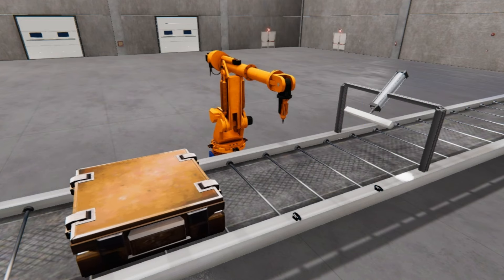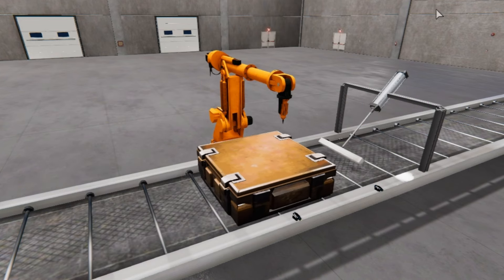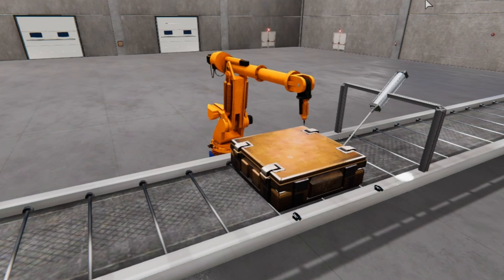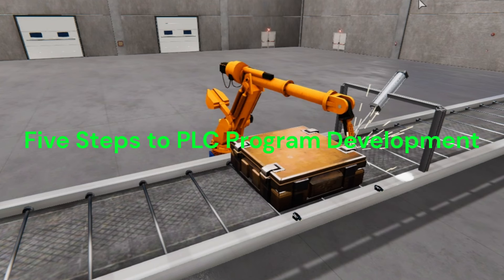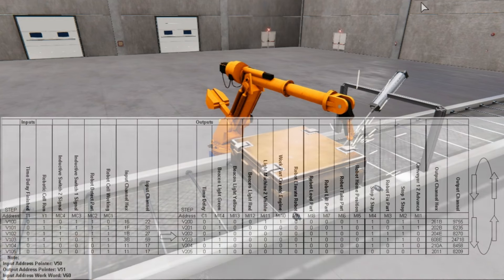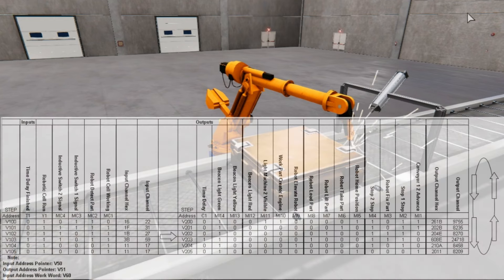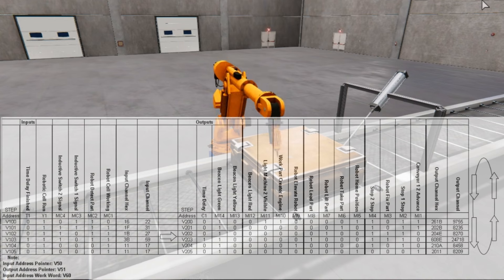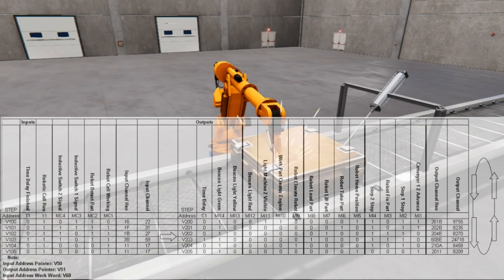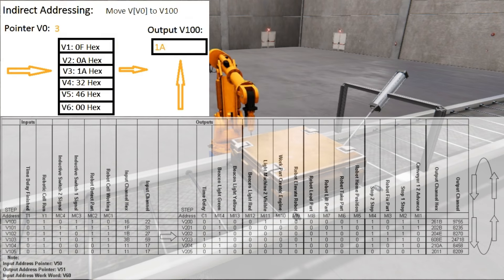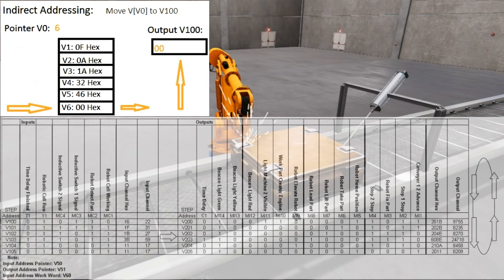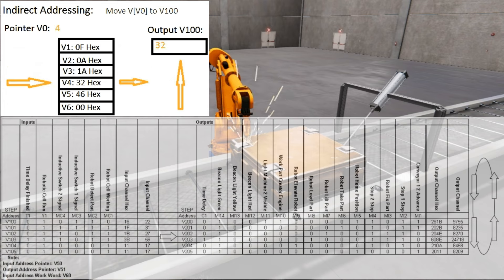The pointer instruction will give you flexibility when programming. Previously, we discussed the five steps to PLC program development. Using a sequence table is an excellent method to determine the states of each input and output in the PLC as we program our machine. The indirect address can take this sequence table and program it directly. The inputs are compared to an input table. If equal, the output pointer will move the output table value to the physical outputs.